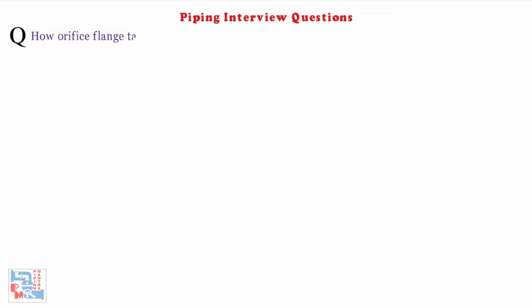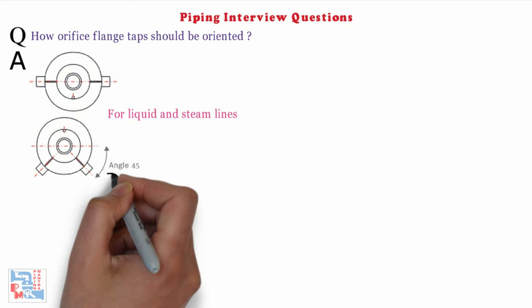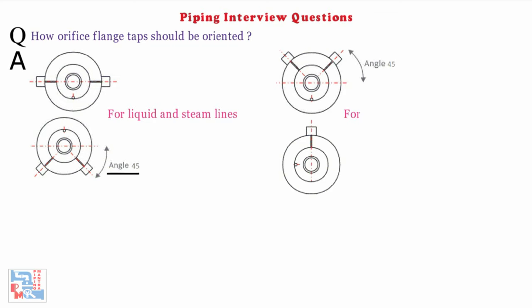How should orifice flange taps be oriented? For liquid and steam lines, it should be horizontal or 45 degrees down from horizontal on both sides. For gas and vapor lines, it should be vertical or 45 degrees to vertical on both sides, tapped at 0.5 inches.